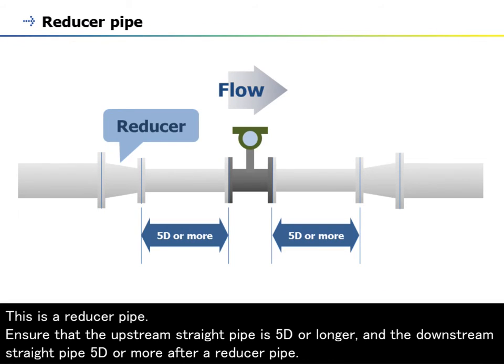This is a reducer pipe. Ensure that the upstream straight pipe is 5D or longer, and the downstream straight pipe 5D or more after a reducer pipe.